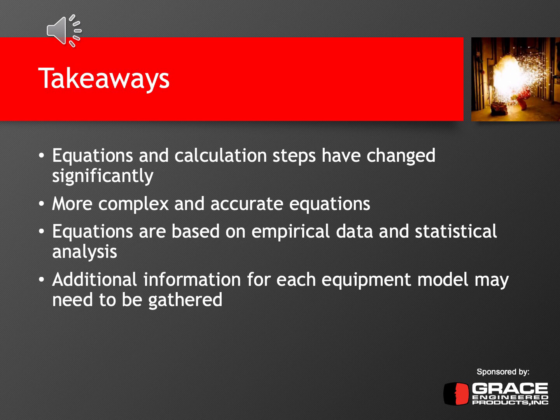Additional information for each equipment model or each piece of equipment may also need to be gathered that is, like I said, in addition to what was done in 2002. Examples of that are the electrode configurations as well as enclosure sizes. And there are correction factors that need to be taken into account when performing the arc flash analysis.